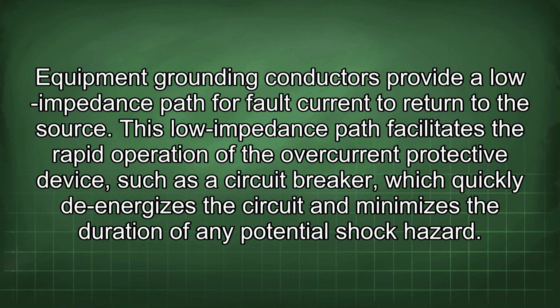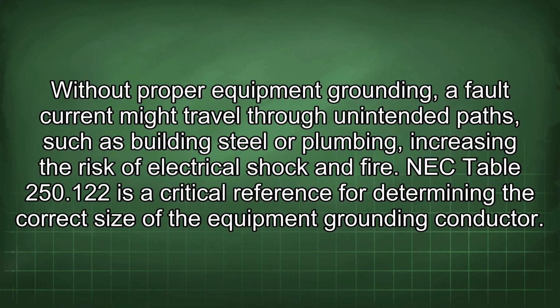Equipment grounding conductors provide a low impedance path for fault current to return to the source. This low impedance path facilitates the rapid operation of the overcurrent protective device, such as a circuit breaker, which quickly de-energizes the circuit and minimizes the duration of any potential shock hazard. Without proper equipment grounding, a fault current might travel through unintended paths such as building steel or plumbing, increasing the risk of electrical shock and fire.